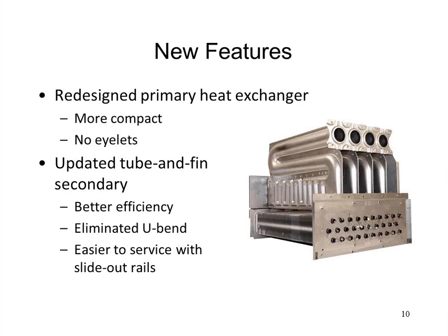So this style heat exchanger, compared to our previous designs, does help it get a little bit shorter. The fin and tube does not take up as much vertical space as our old heat exchanger designs did. That's where you get some of that 5 inches of vertical height savings. And then to squeak more efficiency out of there, that's why they have these turbulators in there, to get another couple tenths of a percent so we can get these things up into the high 90s in terms of efficiency.